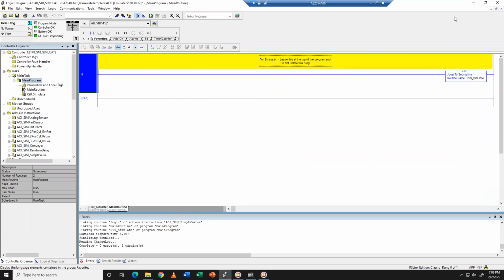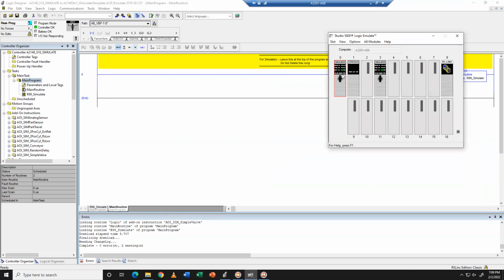I know we touched on this in fundamentals yesterday and last week - I think there was a note about it - but we've got three main states of a processor. There's program mode: there's a key switch on the front of all processors in some way that puts the processor into program. You'll see the status will be teal or cyan, depending on how your eyes work and what you call it. That means you can program and make changes to the controller if the key switch is physically in the program position, pointing to the section that says program.